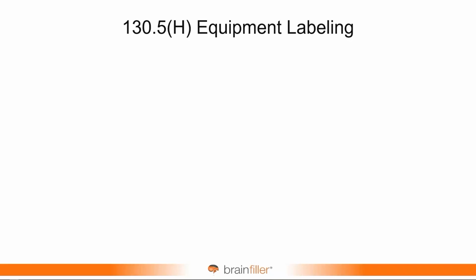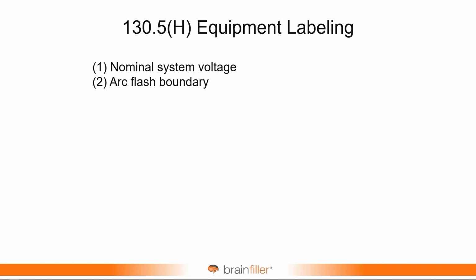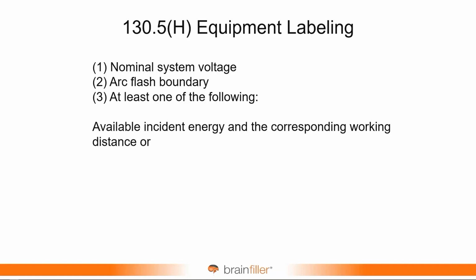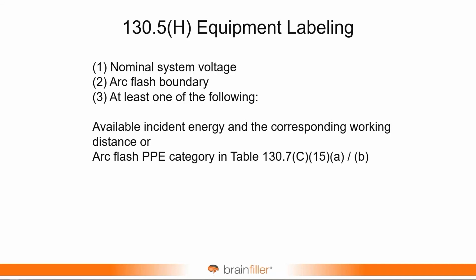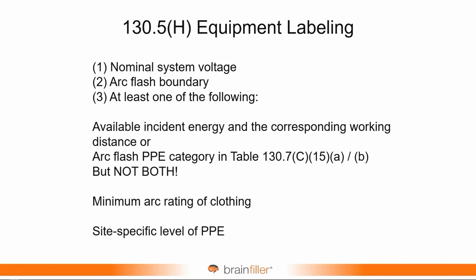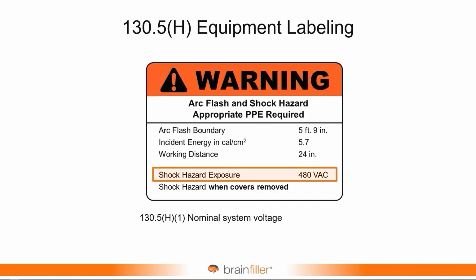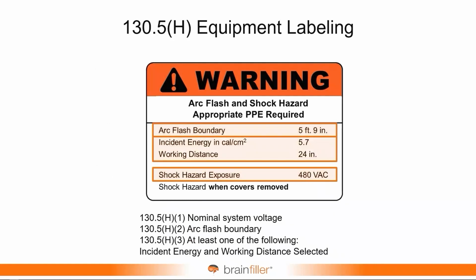Equipment labeling. The requirements for equipment labeling have really not changed much in the last several editions of NFPA 70E. On the label, you're required to have the system voltage, the arc flash boundary, and a method to identify the arc flash hazard, or the PPE, which could include the incident energy and the corresponding working distance, the PPE category, not both, the minimum arc rating of the clothing could be used, or a site-specific level of PPE. So as a minimum, the label may look like this: the system voltage, the arc flash boundary, and then a method to identify the PPE, which in this case is the incident energy and the working distance.